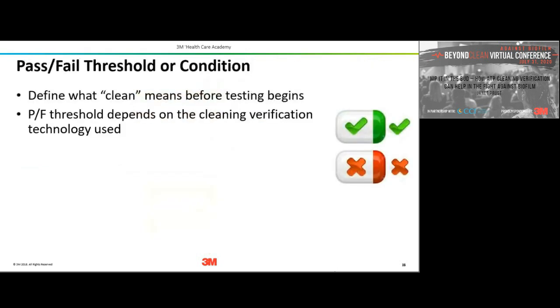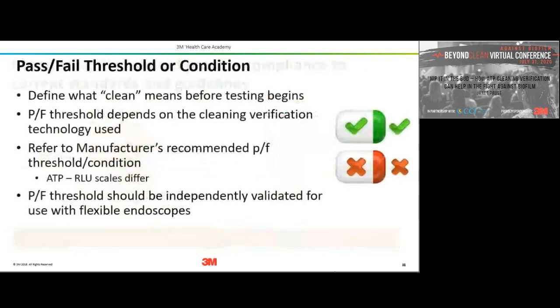For pass-fail thresholds: define what clean means before testing. Values are published in literature and referenced in some standards. For ATP specifically, different manufacturers have different RLU scales, so you can't use a swab from one manufacturer with a luminometer from another — you won't get an accurate result. ATP systems should be independently validated for flexible endoscopes. The monitoring plan needs to be compliant with current standards and guidelines, and manufacturers of these systems have technical data to help you set it all up.